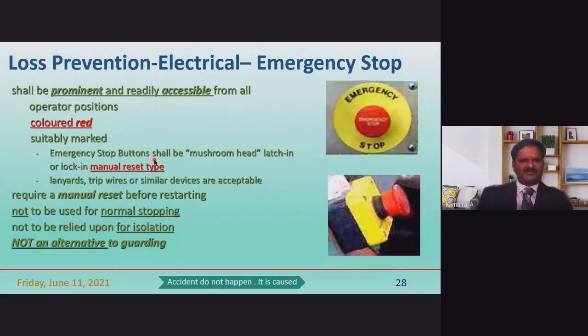A suitably marked emergency stop button shall be mushroom head type, and it is manual reset type. Once activated, it cannot reset automatically, because it may have been triggered by a fault in the atmosphere, or by some small mistake. So we cannot go quickly back to automatic; we need to investigate what happened and why, asking a number of whys, then try to reset it manually.